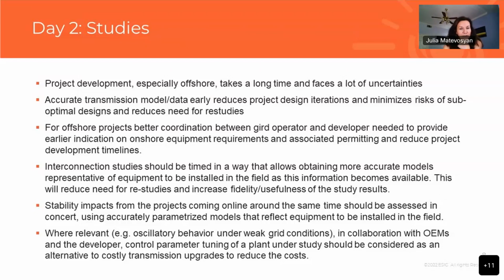And this reduces need for restudies and also increases fidelity and usefulness of the study results, because if you use models of actual equipment that will go in the field with actual settings that will be used there, then the study is more useful. Stability impacts from projects coming online around the same time should be studied in concert, and using accurately parameterized models that reflect equipment to be installed in the field. So basically you need to study a common impact of all projects that are being built around the same time.